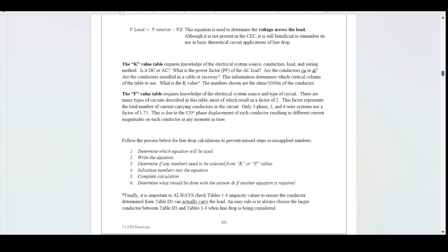The K-value table requires knowledge of the electrical system source, conductors, load, and wiring method: Is it AC or DC? What is the power factor of the AC load? Are the conductors copper or aluminum? Are the conductors installed in cable or raceway? This information determines which vertical column of the table to use. The numbers shown are the ohms per thousand meters of the conductor.